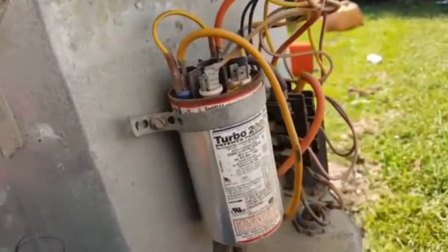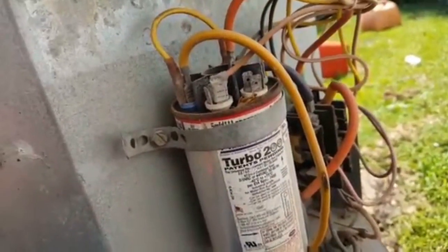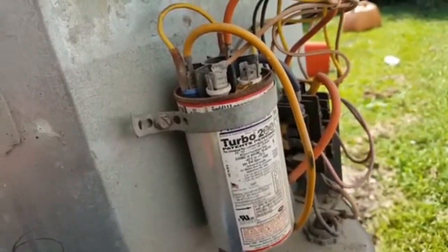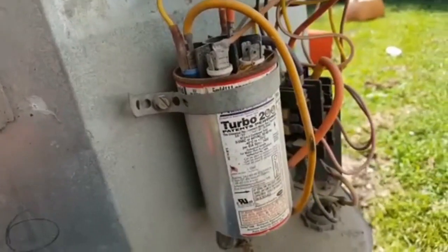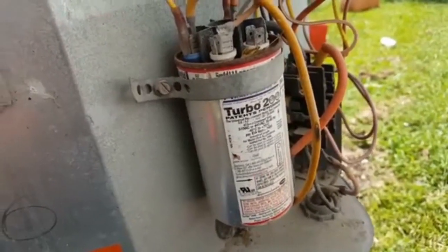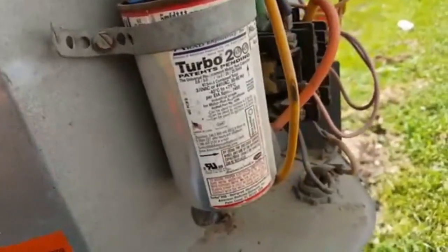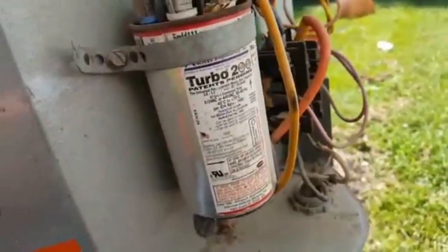Guys, we've got a unit where the compressor and fan aren't running. Now we're going to check out this with an infrared camera and test the capacitor. The fan would spin but wasn't very free spinning, and it didn't take off when I spun it. So we'll check this run cap—I shut the power off to it. We've also got some burning on the contactor, so let's see what's going on.